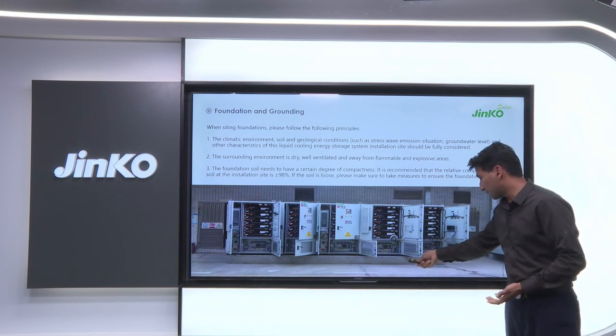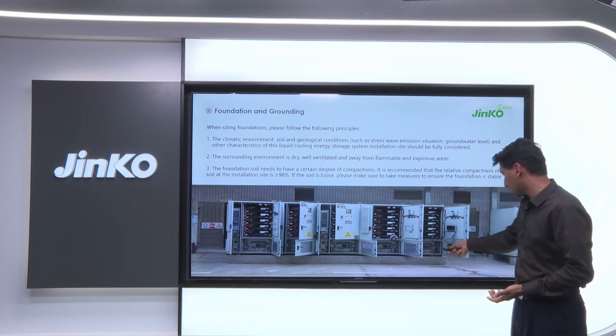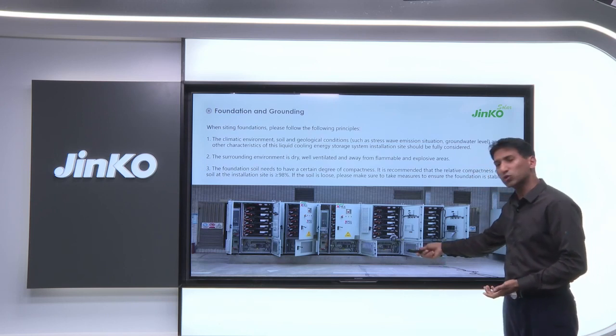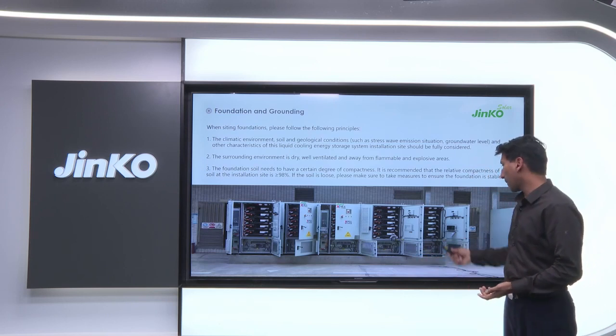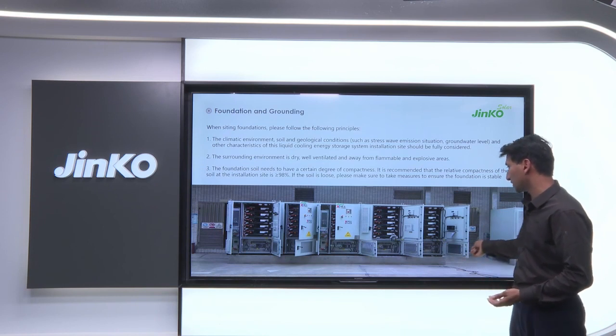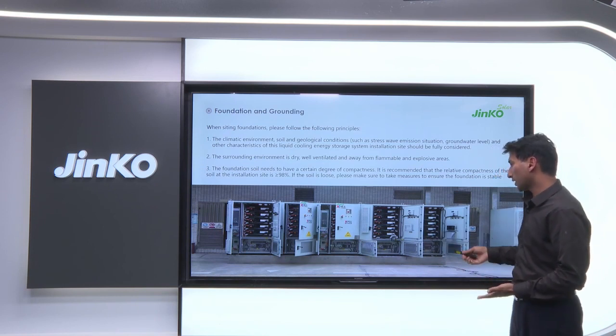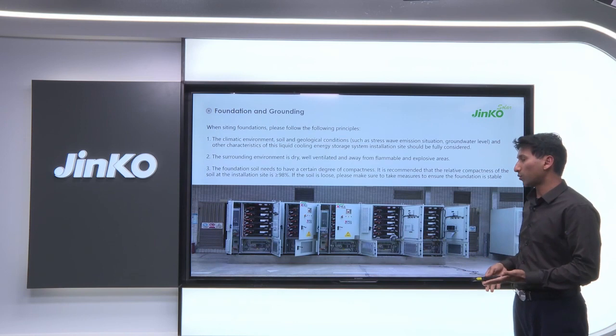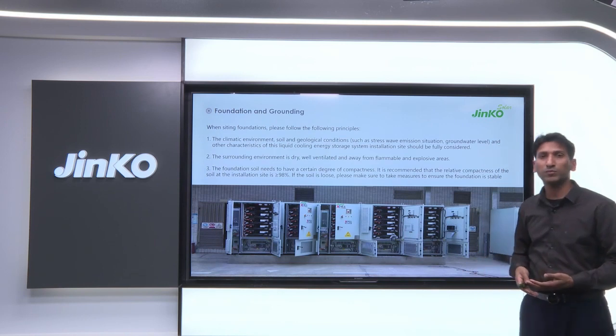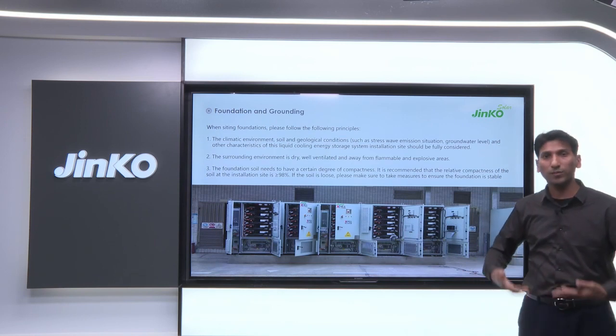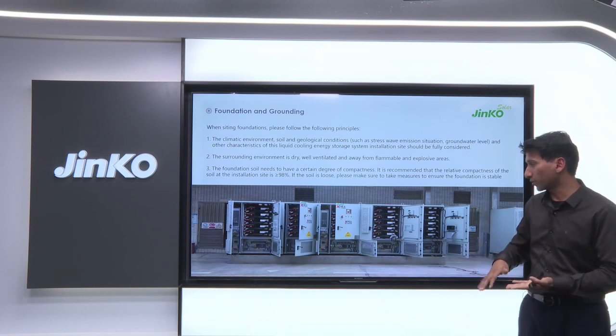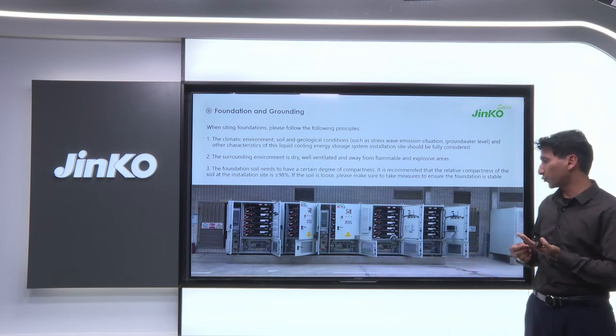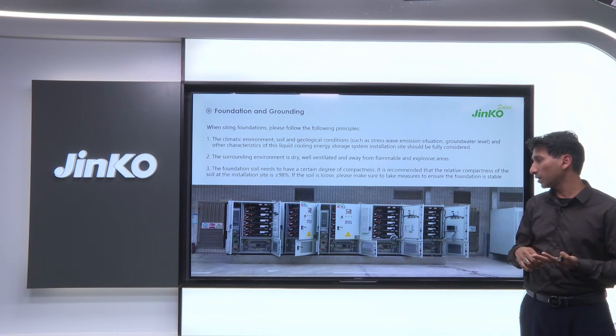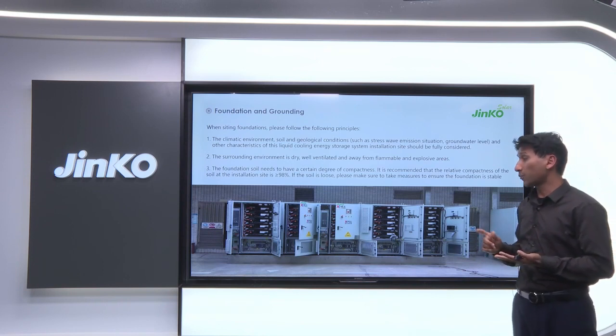When you take cables from inside, if there is no space down there, it becomes very difficult to move the cables. That's why we always suggest to our customers that the foundation should be above the ground level, not on the ground. It should be above for two reasons: one, for the movement of the cable, and the second is the communication cables.